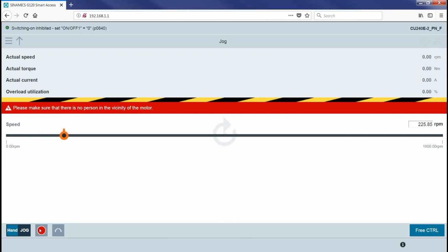Okay, complete. So again, in hand mode, I can give it a speed, say start. I had to stop and then restart. So now it's ramping up to these RPMs. Output torque, current draw from the motor. All right, so I'll stop. I'll free up control.